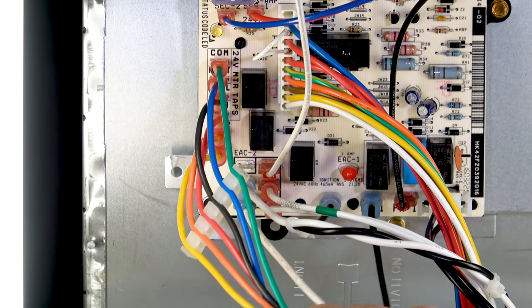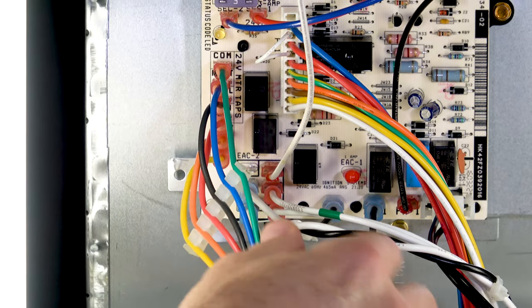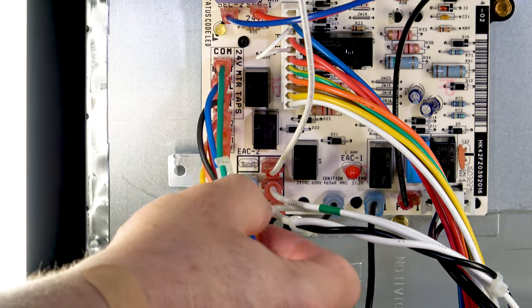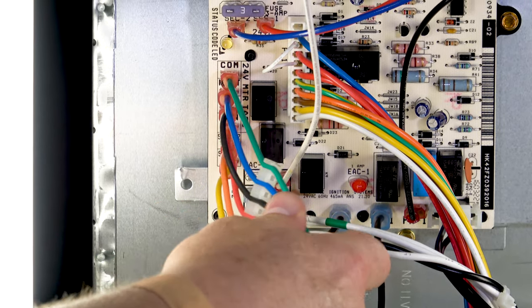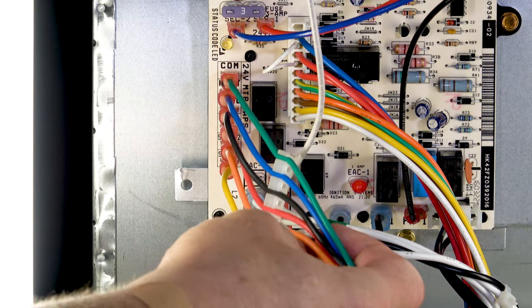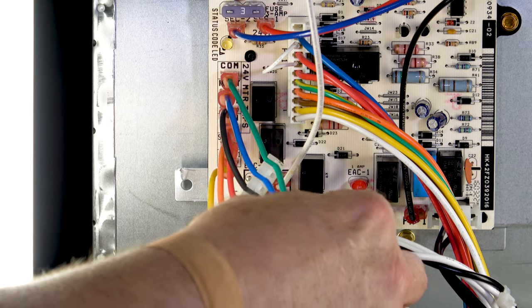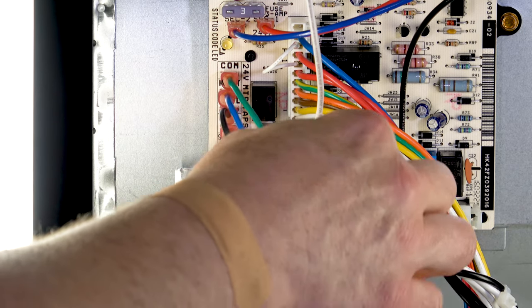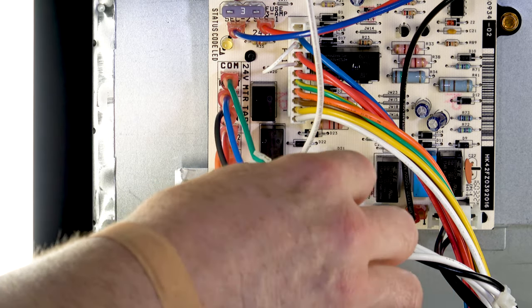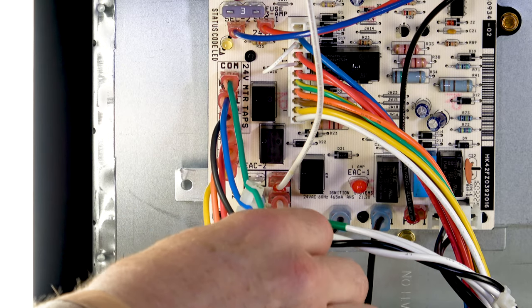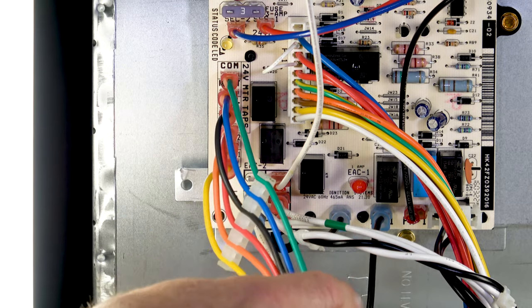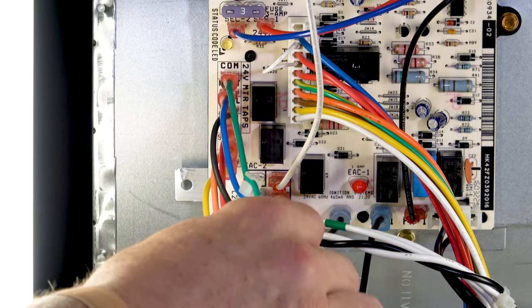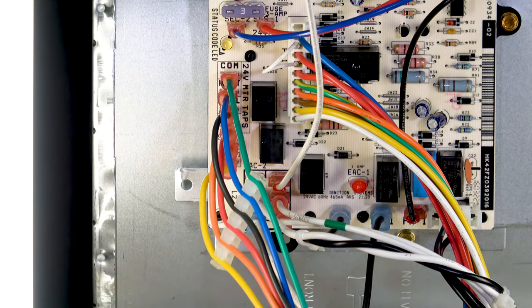As far as your speeds go, on the side of the board you're going to have your five speeds that will control the unit. Of those five speeds you'll also have a sixth wire in that bundle. That six wire is going to be your 24 volt common. The speeds on the x13 motor are 24 volt so you're not going to see the line voltage like you would on a PSC motor.